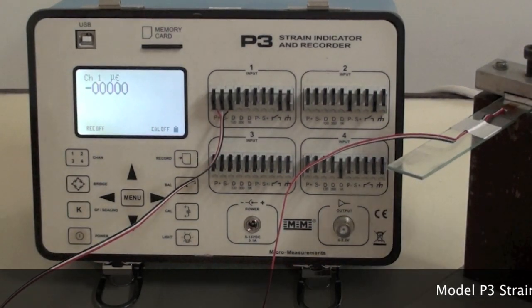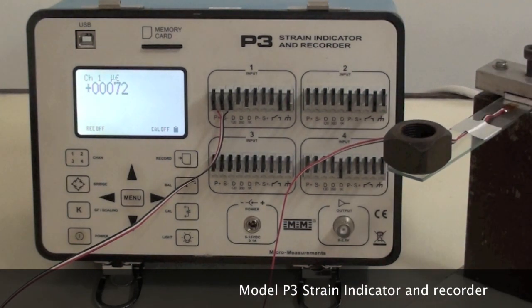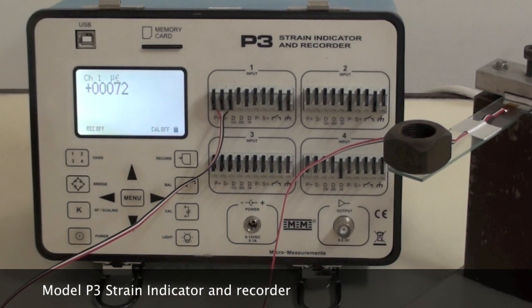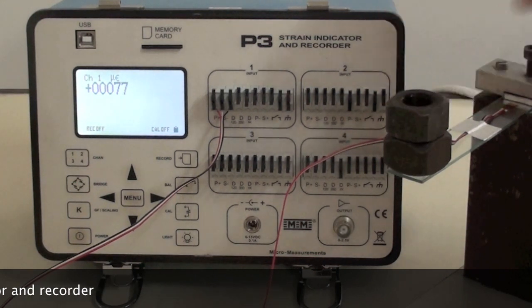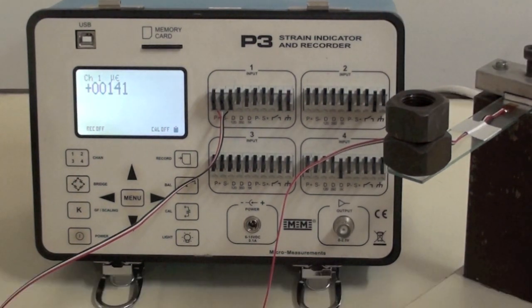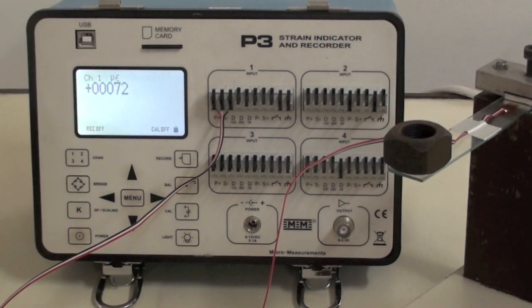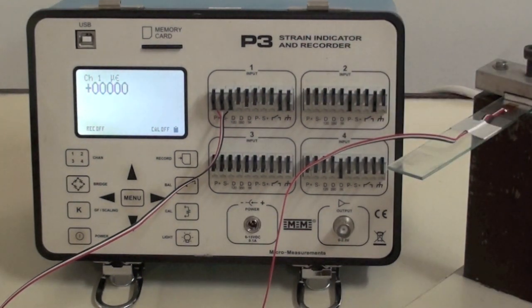The gauge is connected to a model P3 strain indicator and the beam is loaded to see if gauge installation is satisfactory. An unchanging zero after balancing the reading, stable and repeatable readings of strain under load, and a good return to zero when unloaded indicates reliable strain gauge installation.